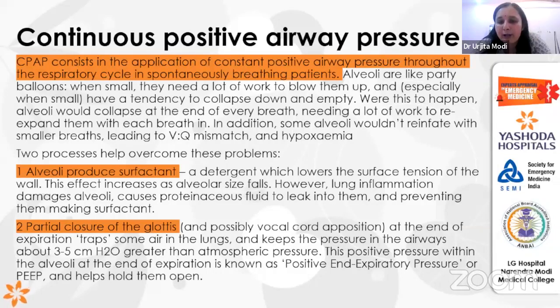Again, whenever you are going to use CPAP, you need a ventilator, a machine which generates the flow. A continuous generation of flow is needed, and this flow must be more than the peak inspiratory flow rate, and it has to be the same at all times. Otherwise, there is a fluctuation of the pressure. So this circuit will give us some idea. The flow generator is here, a tight fitting mask on the patient's face, and there's a valve to regulate the pressure.